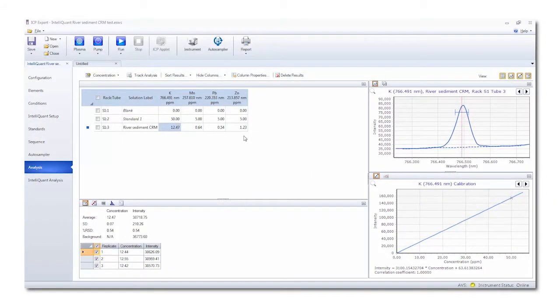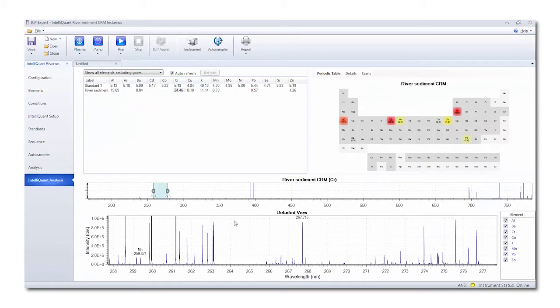Reviewing the results, the recovered elements on the analysis page match the CRM values. Now to rapidly review everything that was in the sample, simply click on the IntelliQuant analysis page. Full spectrum capture is displayed and also semi-quantitative values. Looking at the results, it can be seen that many elements match the CRM values to a high level of accuracy. In fact, the presentation of the semi-quant data into the periodic table heat map makes it very rapid to understand what is present and how much. Dark red is high concentration and yellow is low concentration.